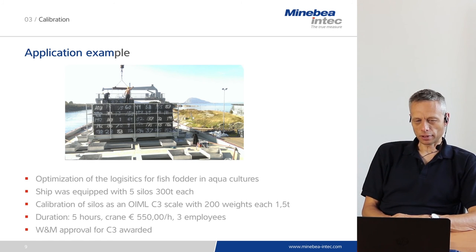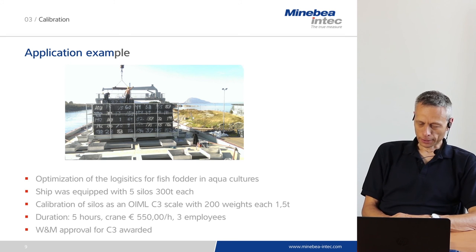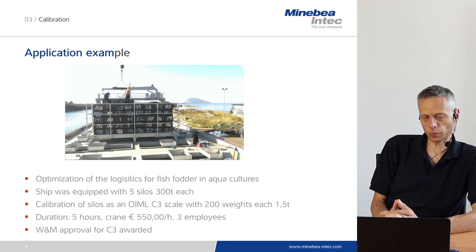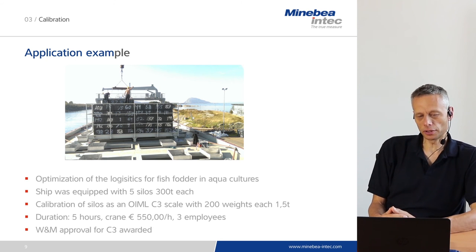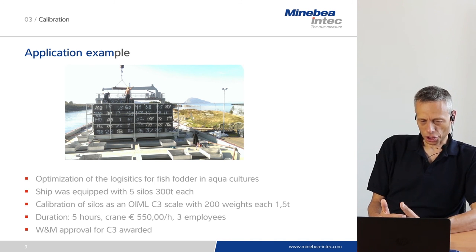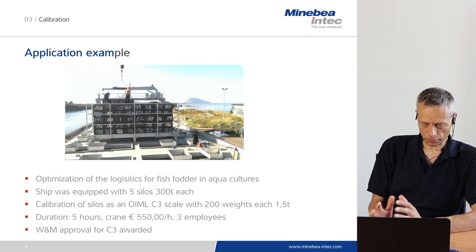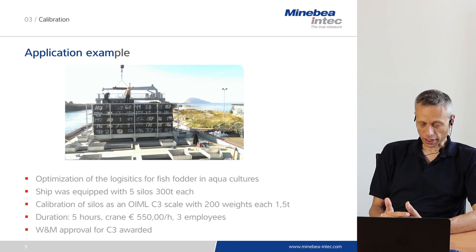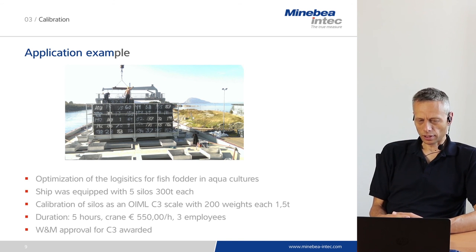Finally, I would like to show you an application example of a calibration by weights, to give you an impression of the amount of work and material necessary to calibrate high capacity silos. The application is on a boat — a vessel used for fish fodder in aquacultures in Norway. The purpose was optimization of logistics to deliver fish fodder to fish farms. This ship was equipped with five silos of a nominal capacity of 300 tons each, and the whole system needed legal approval to deliver fish fodder directly from the boat to the fish farm by weight.